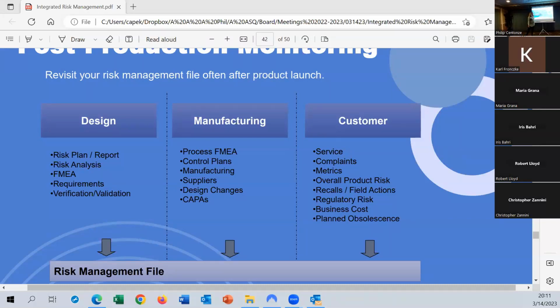And then obviously any complaints or service metrics, if we figure out that something keeps failing in the field and we need to replace it, we should be adjusting the probabilities for our FMEAs and our hazard analysis based on all of the information that we have available to us. So the risk management documents are living documents. They continue to be updated till the product is obsolete and no longer used.